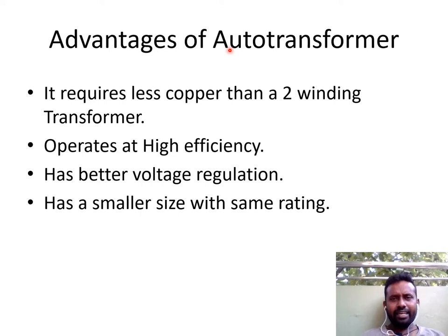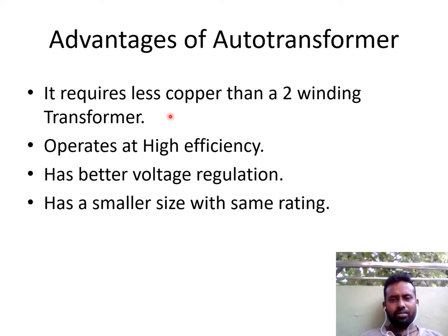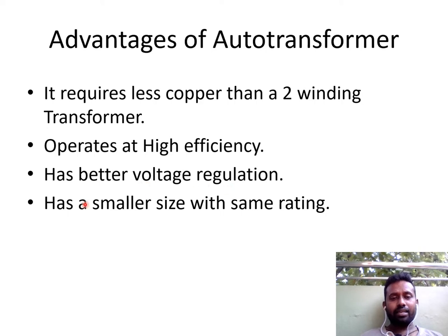Why do we study the auto-transformer? What are the advantages of going for an auto-transformer? It requires less copper than a two-winding transformer — this is one of the main advantages, so the cost is reduced. Also, the efficiency of this auto-transformer is very high, and it also has better voltage regulation. It is of smaller size with the same rating as a two-winding transformer. These are some of the advantages of the auto-transformer.